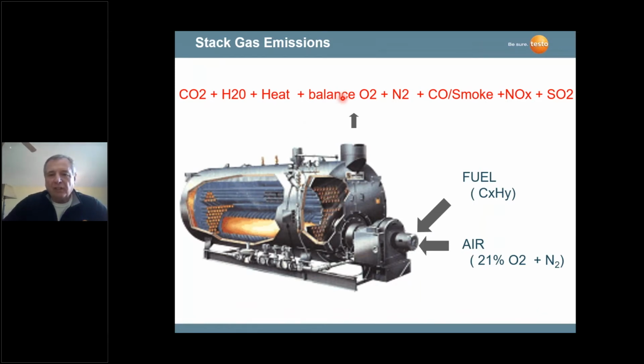Balance of oxygen. We use a combustion analyzer. We're sampling the flue gases. We're going to get a balance of oxygen because we're not using all the 21% oxygen in the combustion process, but we do have a balance of oxygen coming out the stack, and that's important. We'll go through that in the next couple of slides. Nitrogen, carbon monoxide, smoke. Carbon monoxide and smoke are found in oil. Primarily, carbon monoxide is found in gaseous fuels as well as oil. Smoke is typically an indicator of poor combustion in oil burners. And then we have the two gases called NOx and SO2. This is nitric oxide. This happens to be sulfur dioxide. These are used on your large boilers.